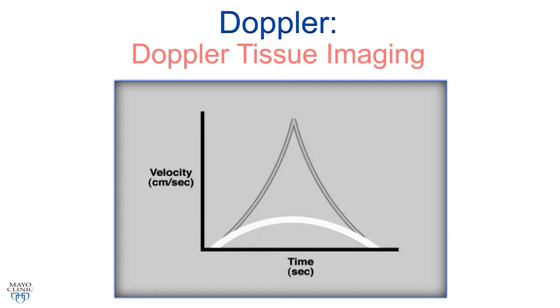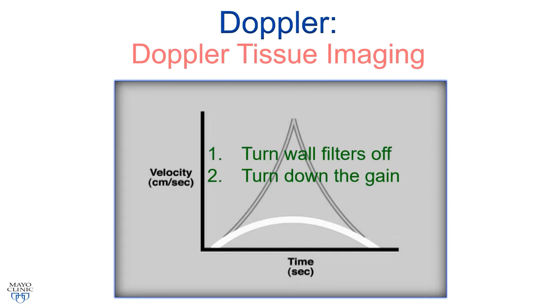Doppler tissue imaging is really a way of measuring myocardial velocities. This schematic illustrates the principles behind Doppler tissue imaging. The white bar represents the high intensity but low velocity signals from the myocardial wall. The gray bar represents the higher velocity but lower intensity signals from the blood pool. In spectral blood pool Doppler, the wall signal is considered noise, so we turn the wall filters on. But in Doppler tissue imaging, that is the signal we're interested in — so we turn the wall filters off and turn down the receiver gains.